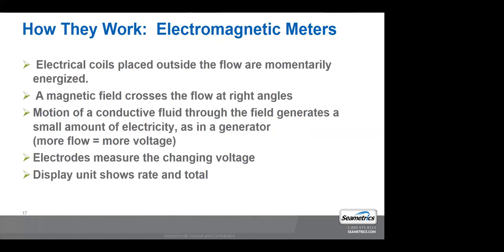There's electrical coils outside the flow, those are energized. Magnetic field crosses the flow. It's reading the conductivity in the fluid that's going through it. So mag meters work very, very well on well water, on dirty water. They wouldn't work on something like deionized water. They need those minerals running through the water.